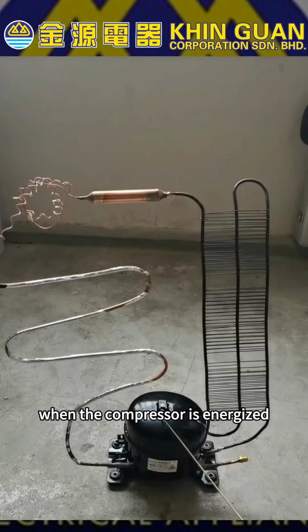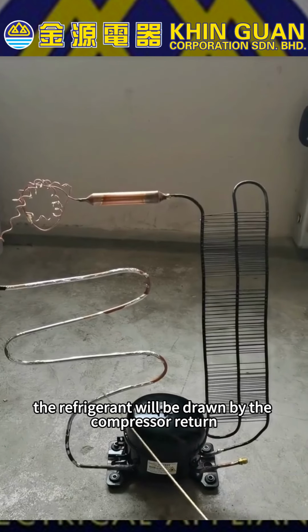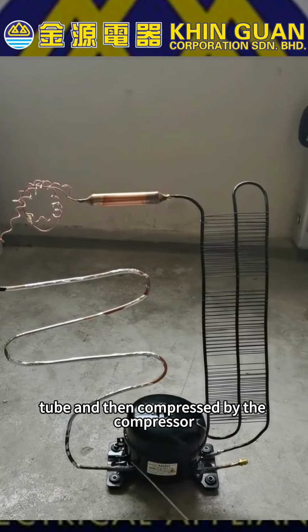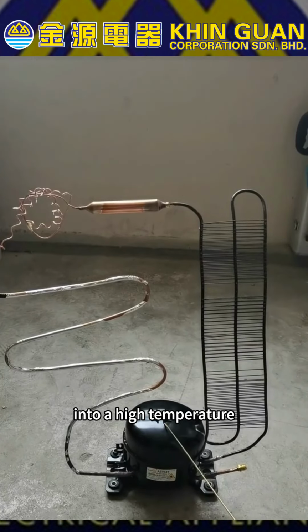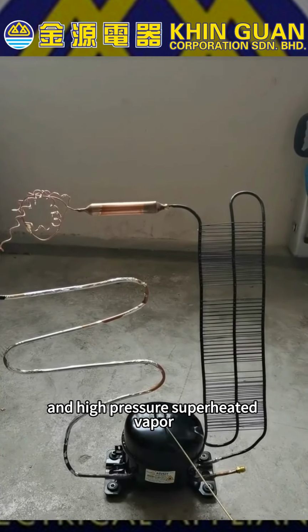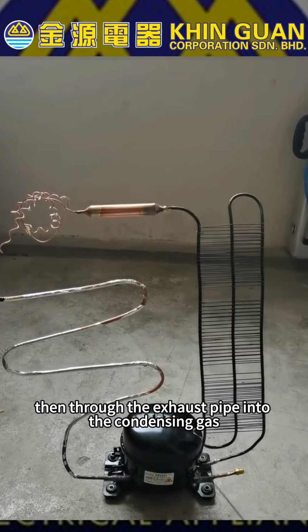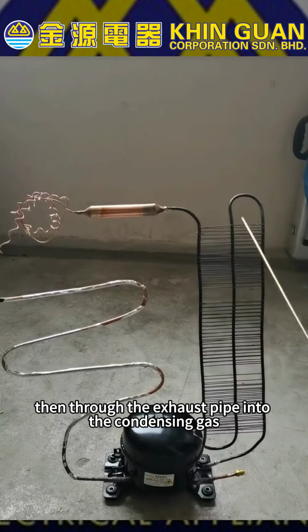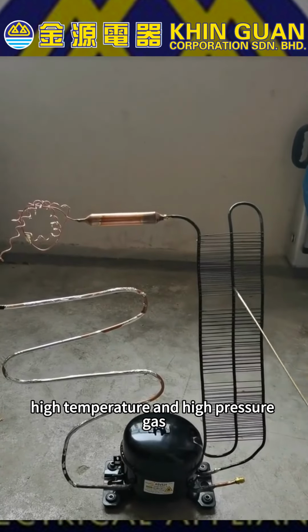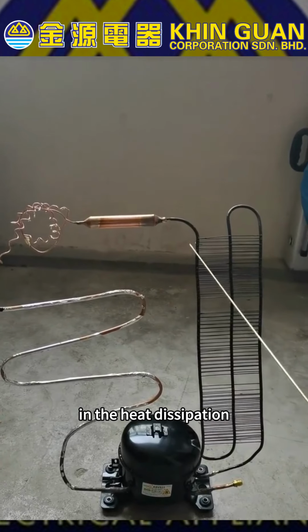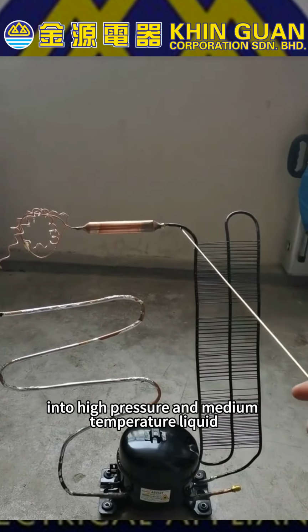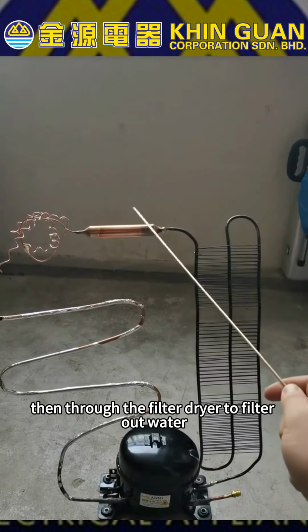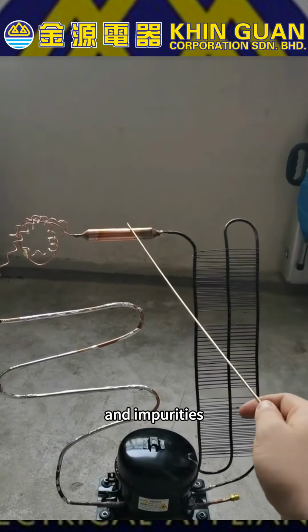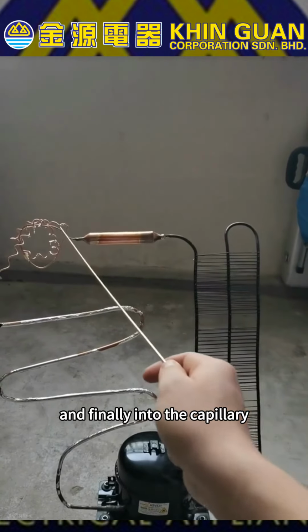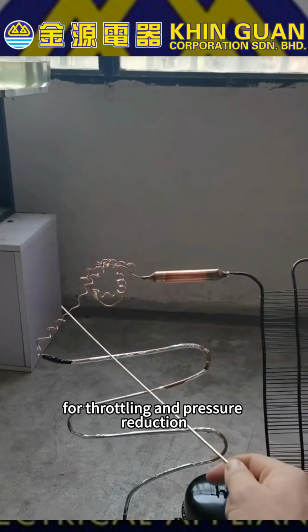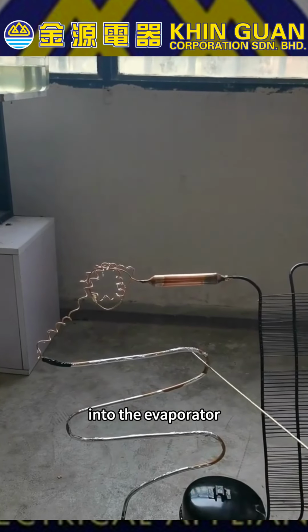When the compressor is energized, the refrigerant will be drawn in by the compressor return tube and then compressed by the compressor into a high temperature and high pressure superheated vapor. Then through the exhaust pipe it goes into the condenser. The high temperature and high pressure gas in the condenser dissipates heat and becomes a high pressure and medium temperature liquid. Then it passes through the filter dryer to filter out water and impurities, and finally enters the capillary for throttling and pressure reduction, flowing into the evaporator.